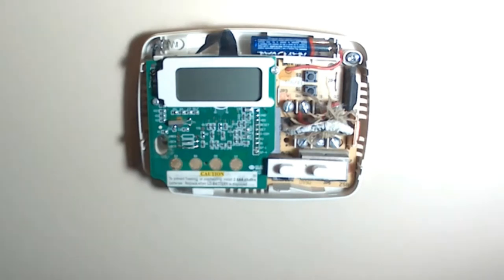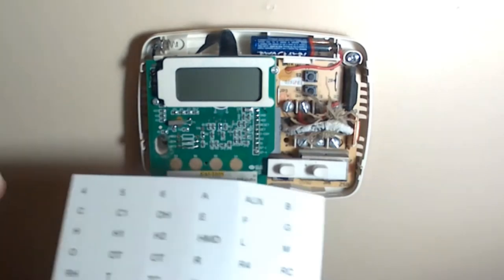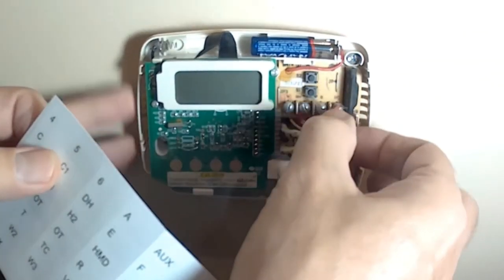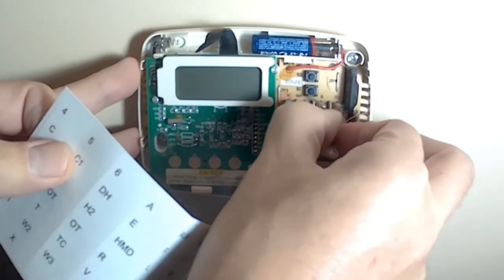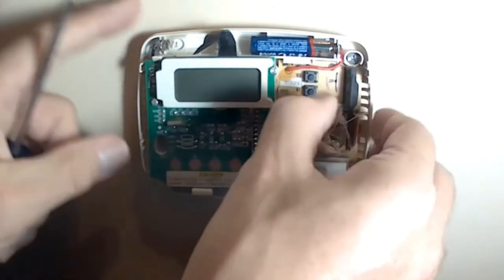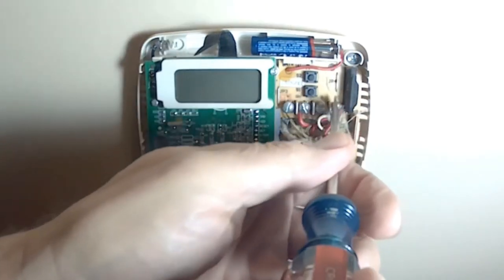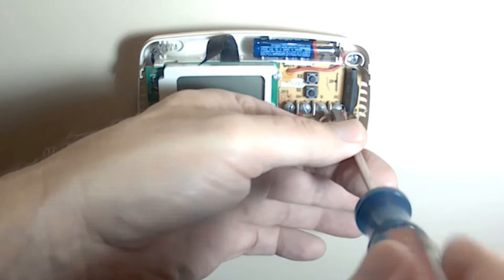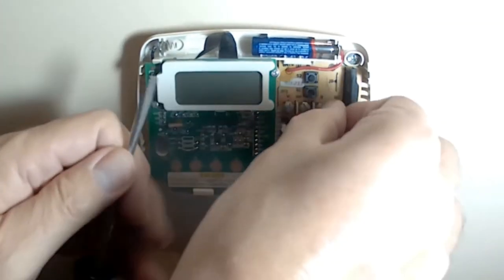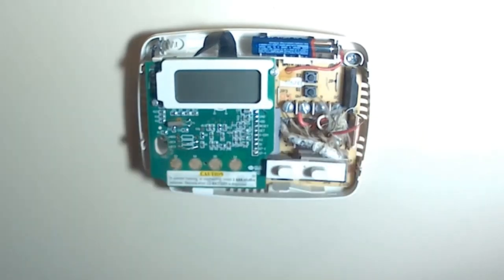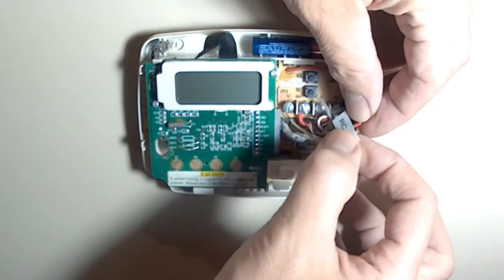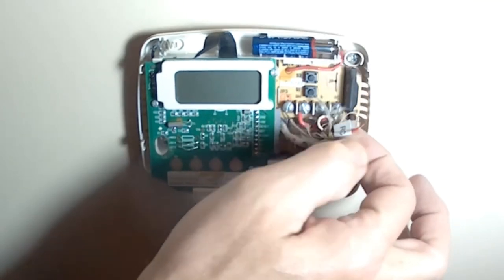And your new thermostat comes with these labels so you can label your wires. So we are going to gently pull this away. We are going to hook up the same way it was before. We have this red wire. It goes to RC. So I am going to take that red wire off and label it RC. It is a good idea to take a picture before you do all this stuff.